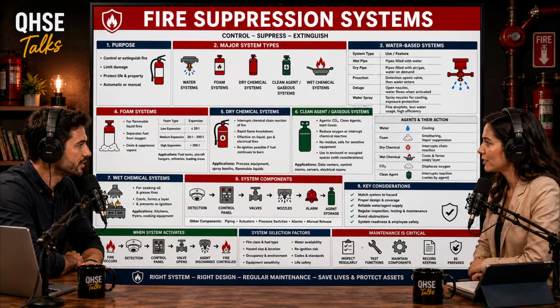So if someone opens an industrial oven door, the absolute temperature might not reach the 135-degree fixed limit, but a sudden flash fire from a chemical spill would instantly trigger the rate of rise. Precisely. And finally, we have flame detectors. These activate in response to radiant energy, specifically ultraviolet or infrared light generated directly by the combustion process. They're literally just looking for the light signature of a flame. Yes. And these are incredibly fast. They don't have to wait for heat to rise or smoke to drift. They operate at the speed of light.